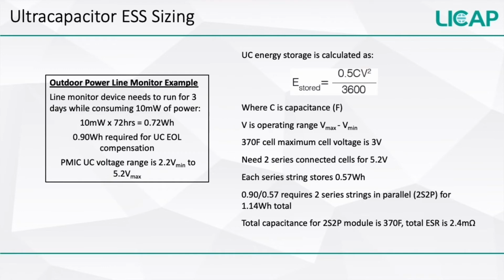Some things to think about when sizing an energy storage system with ultracapacitors as the primary storage device. Here's an example of an outdoor power line monitor that needs to run for about 3 days while consuming 10 milliwatts of power. That 3-day period would be considered the standard blackout period, where you could be sitting without any charge current being supplied to the ultracapacitors.